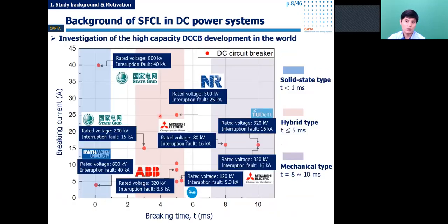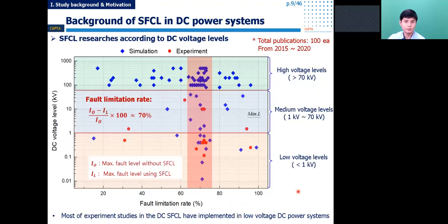This slide shows the investigation of high capacity DC circuit breaker development in the world. The main parameters of a DC circuit breaker are the breaking current level and the breaking time. The current designed circuit breakers can break fault current up to 40 kiloamperes with a time of less than 10 milliseconds.